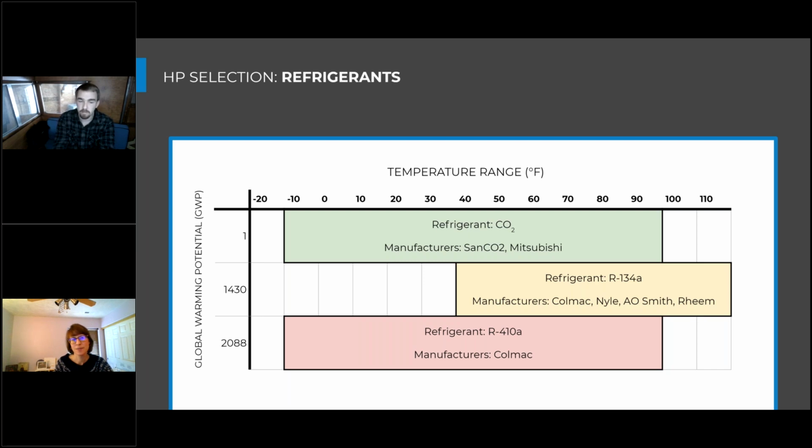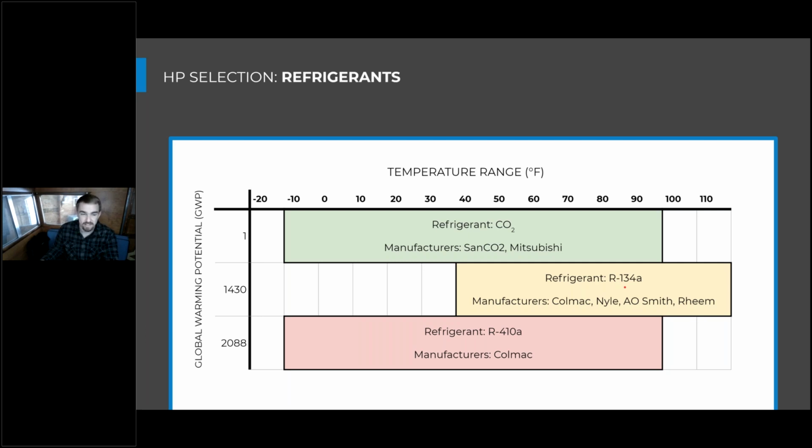So be cautious though. If you have a max leaving water temperature of, say, 180 degrees, as you know, Colmac CXAs have that, but they only have that if your air temperature is somewhere between 60 and 70 degrees, right? So if you rely on your system making 160, 170 degree water, you need to make sure that the air temperatures are actually accommodating the heat pump's ability to do that. Very interesting, that correlation there. All right, all the questions. Thanks there. Yeah, great questions.